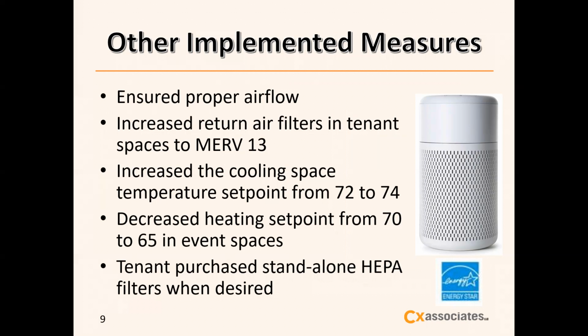And we ensured that the housing of the air handler filters and energy wheels were well sealed inside the air handling units so that the air doesn't bypass the filter mediums. We further installed MERV 13 filters in the return ductwork, and to raise the building relative humidity levels, we increased the cooling space temperature from 72 to 74 degrees. To reduce energy consumption, we decreased the heating set point in the event spaces, which were empty, from 70 to 65 degrees.